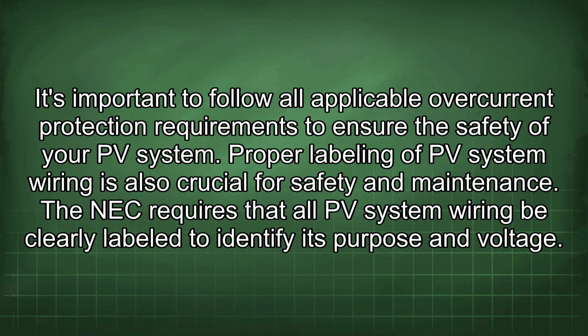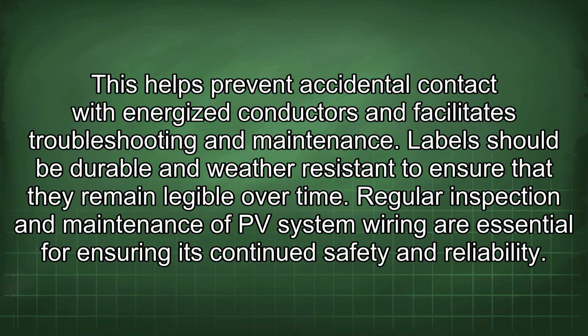Proper labeling of PV system wiring is also crucial for safety and maintenance. The NEC requires that all PV system wiring be clearly labeled to identify its purpose and voltage. This helps prevent accidental contact with energized conductors and facilitates troubleshooting and maintenance. Labels should be durable and weather resistant to ensure that they remain legible over time.